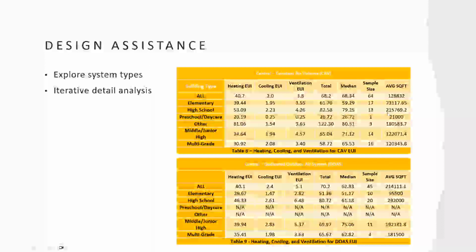versus 215,000. Okay, so you can see this is a higher average square foot, and it's more efficient than this one. So it's actually, we're saving even more energy than we would if we're using a building of this size with this system type. Okay, so if we increase the average square footage to match this, this would significantly go up by at least probably 8 points or so.